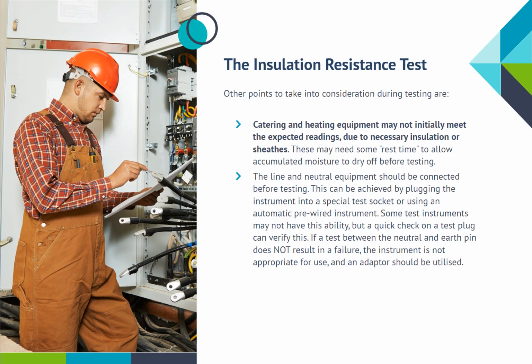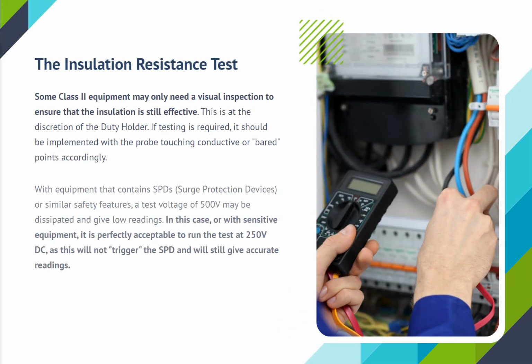Some test instruments may not have this ability, but a quick check on a test plug can verify this. If a test between the neutral and earth pin does not result in a failure, the instrument is not appropriate for use, and an adapter should be utilized. Some Class II equipment may only need a visual inspection to ensure that the insulation is still effective. This is at the discretion of the duty holder. If testing is required, it should be implemented with the probe touching conductive or bared points accordingly.